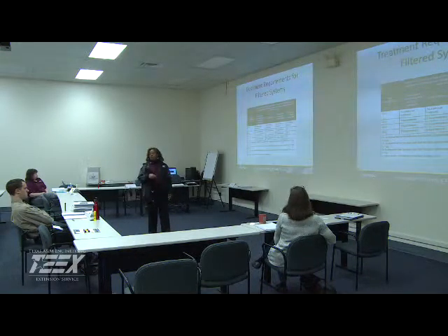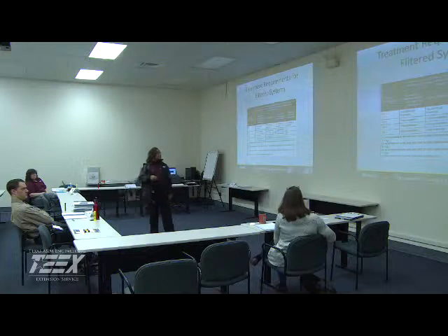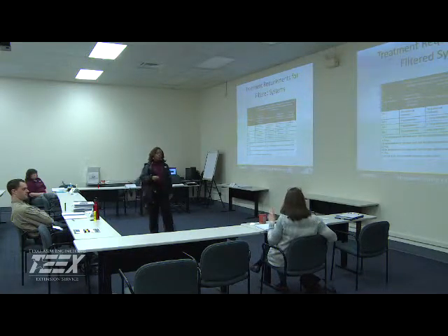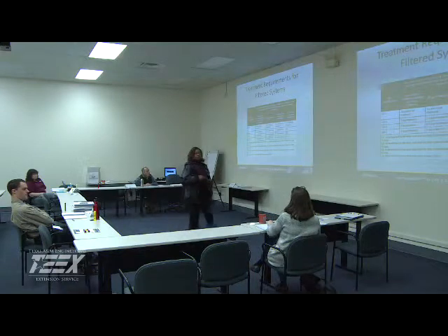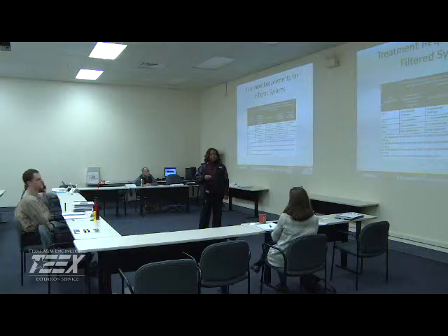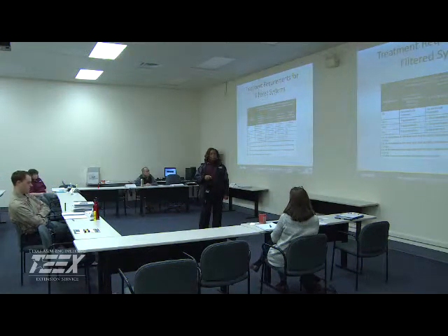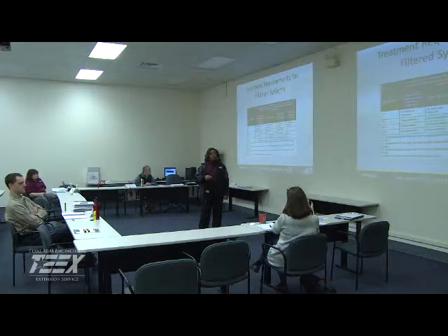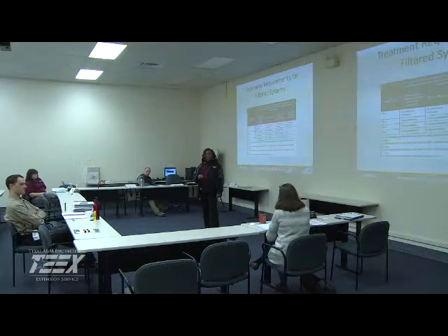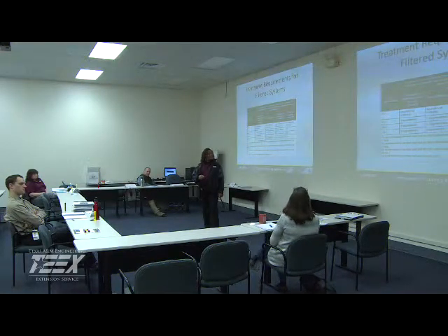So where did you all fall? We have one water system that fell in bin 2, and they were conventional filtration. And they opted to get their 1 log credit. They got a half a log by doing source water protection upstream, and they have given a lot of money to fencing around cattle farms, mushroom operations, and riparian buffer zones and things like that.